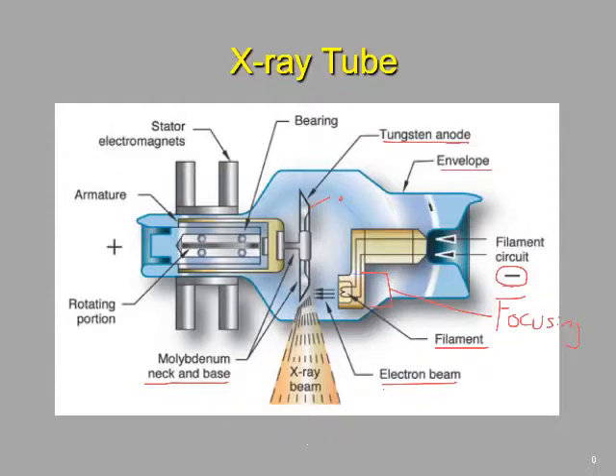That's why we have this heavy lead housing around the x-ray tube — to protect us from any x-rays being produced in a direction other than what we want. The x-ray beam will exit through a window made out of aluminum. In this area there is an aluminum window in the housing that permits x-rays to exit the tube and go directly into the collimator.